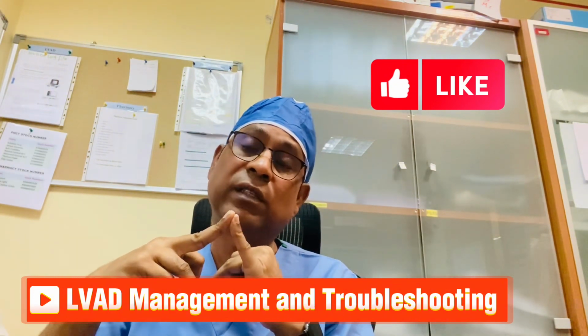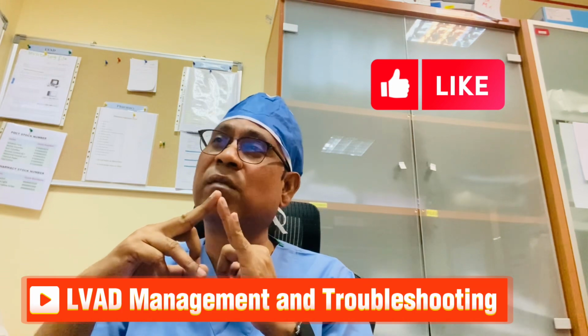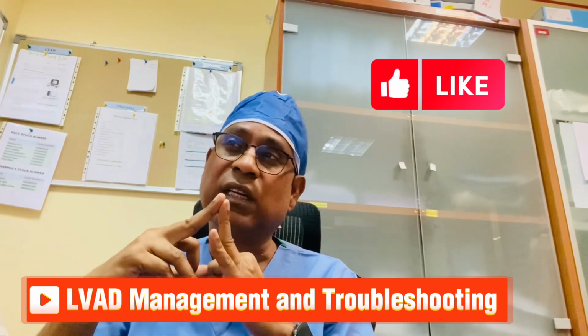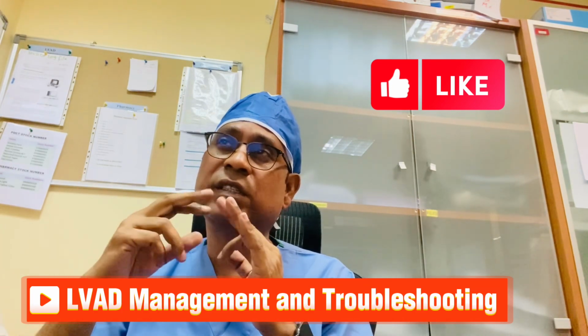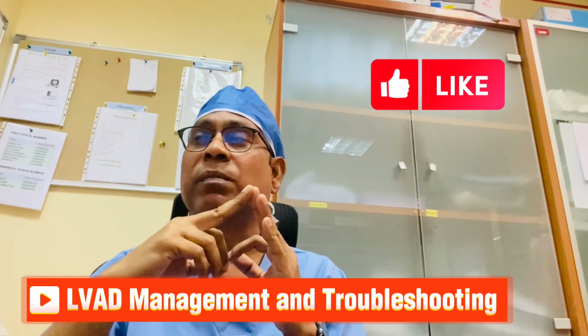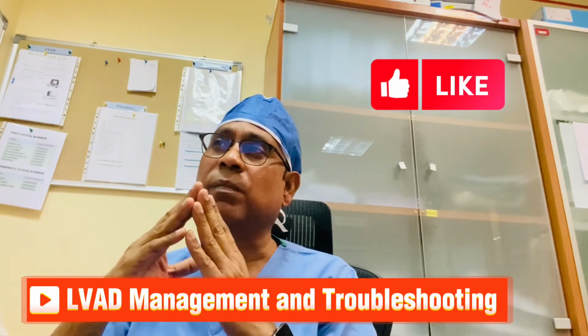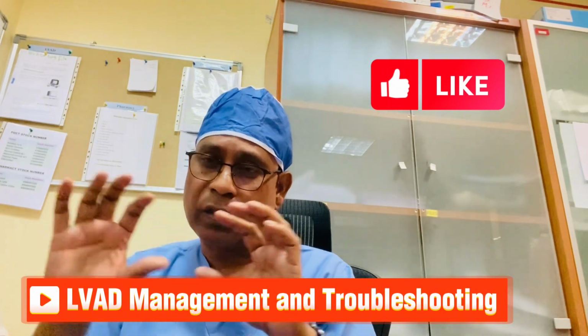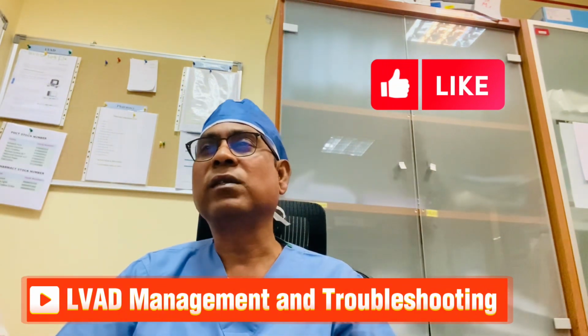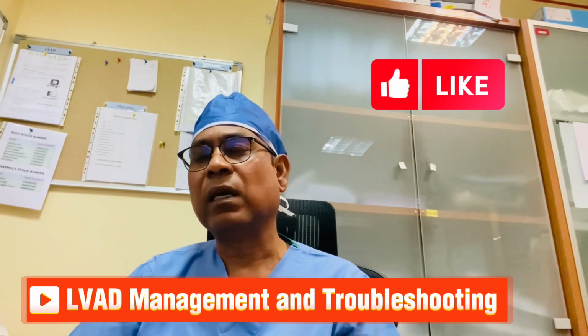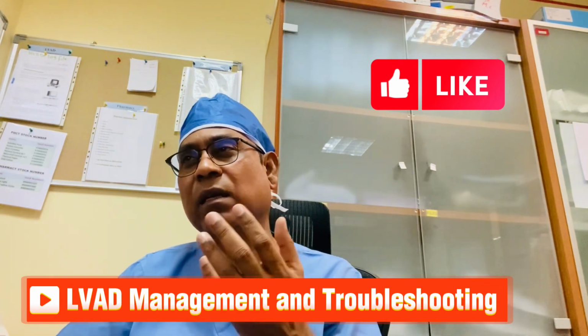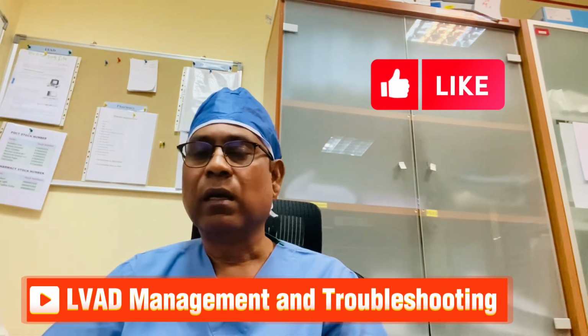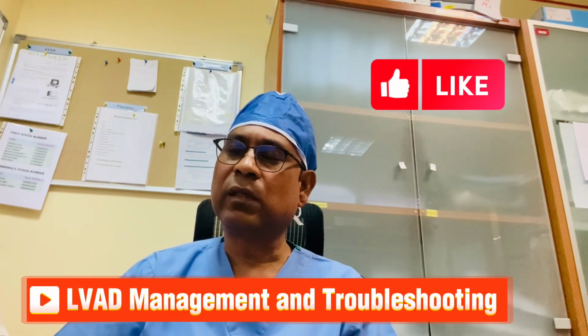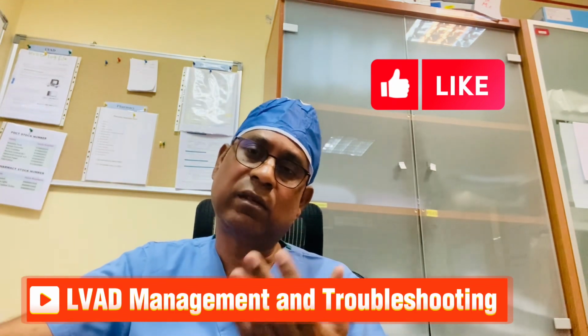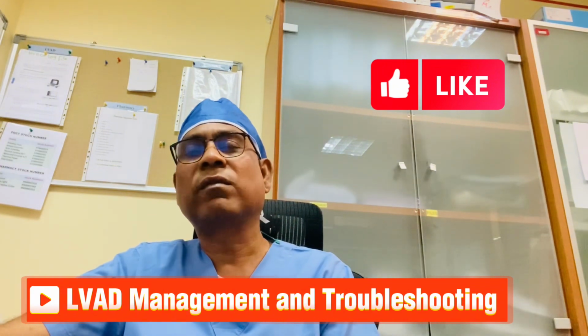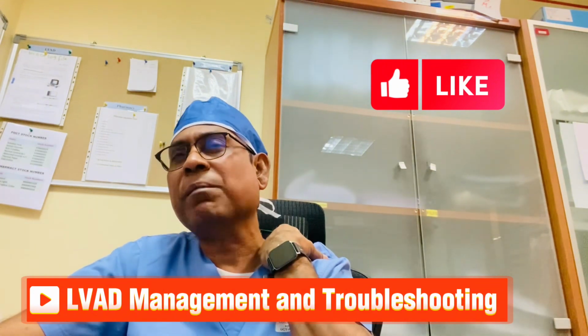Pump speed means revolutions per minute. We see the patient's power. Power means the watts, how much energy the motor is taking. Pulsatility index is the pulse index, and of course the estimated pump flow on the pocket controller. Then we do an additional review of any recent alarms, and in the meantime we also check whether any alarm is there in the log events. We go through that so that we can get proper information related to the patient's details. So we'll talk about the pulse index, PI.